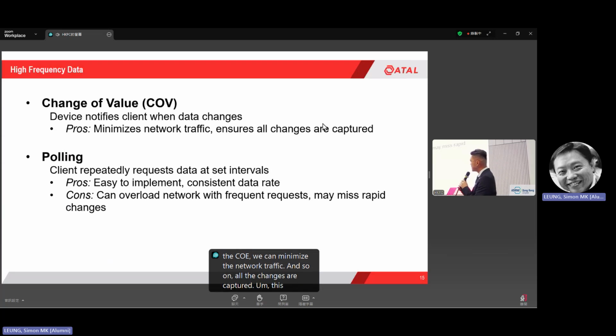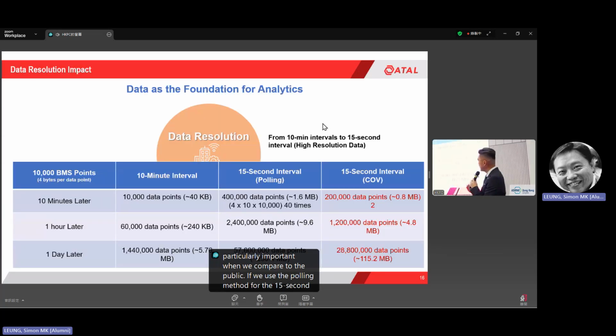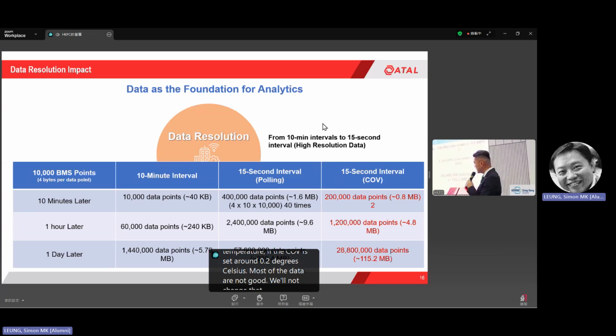This is particularly important when we compare to polling. If we use the polling method for the 15-second data log, as I said, for 1 day, it will be around 60 million data. But using the COV, even with a 15-second interval, the data size is significantly reduced because some data will not change from time to time. Let's say the status may only change a few times a day. For the temperature, if the COV is set around 0.2 degrees Celsius, most of the data will not change that frequently. So the data size can be significantly reduced. That is how we can obtain the high frequency data.